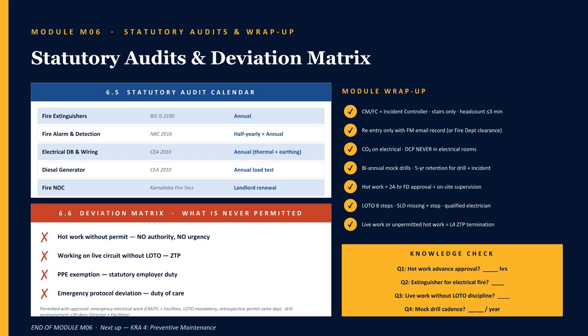Diesel generator under CEA 2010, annual load test plus logbook. And the fire NOC under the Karnataka Fire Services Act, landlord renews, but TeamFit tracks validity and escalates delays. All certificates retained for 5 years. Now the deviation matrix, and this is the most important slide in the entire module. 4 things are never permitted under any circumstance.